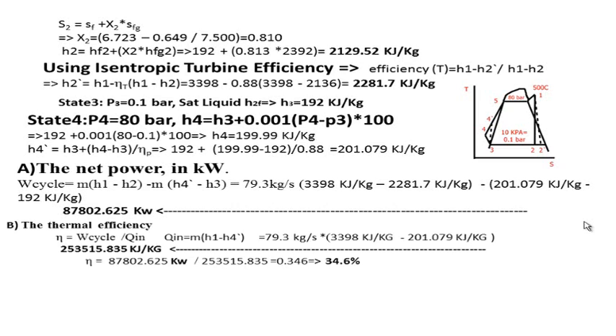The thermal efficiency, based on the equation of thermal efficiency, which is the work net divided by the Q supply or the heat supply to the cycle. The heat supply in the boiler equals mass of steam times H1 minus H4 prime, which equals about 253,515 kilowatt. Based on these two numbers, the net power and the Q added, we can find the efficiency, which is 34.6%.